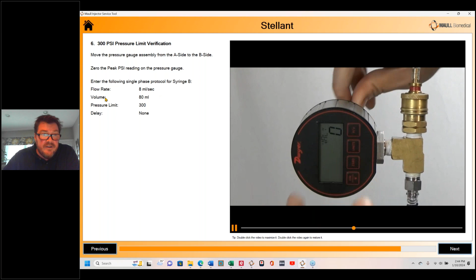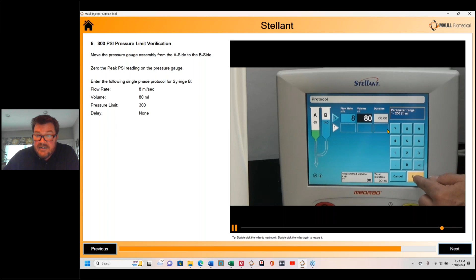And then we're going to repeat this on the B side since we selected a dual head syringe. We just take this pressure gauge off the A side, move it to the B side. We're going to zero the pressure gauge out. And then we're going to change our protocol on the display. Green means contrast. Now we're going to do it for the blue saline. So we're going to change everything. We're going to make it a saline injection and put 80. And then we still have the 300 psi. Now we're set up to do the next injection.